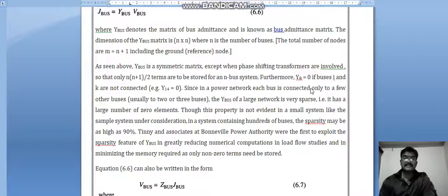So that only n times (n plus 1) by 2 terms are to be stored for n buses system. Furthermore, Yik equals zero if buses i and k are not connected. For example, Y14 equals zero. Since in the power network each bus is connected to only a few other buses, the Ybus of a large network is very sparse.